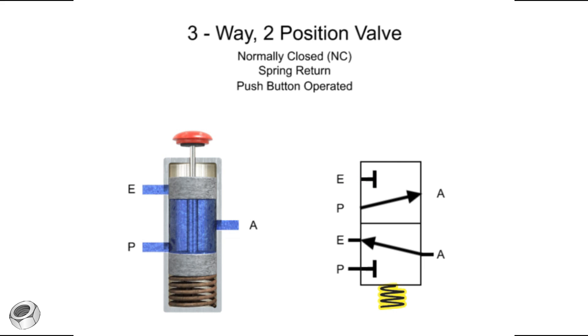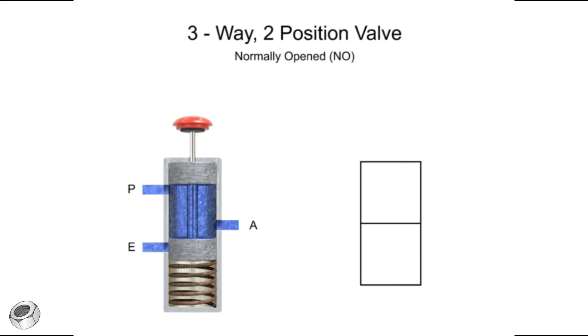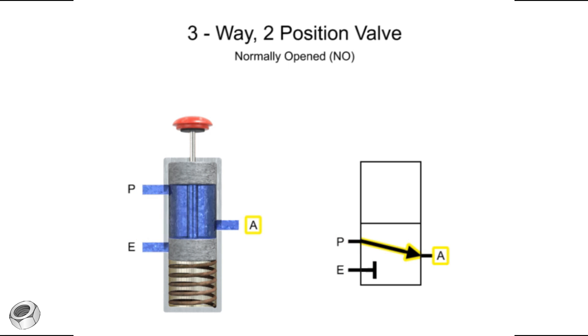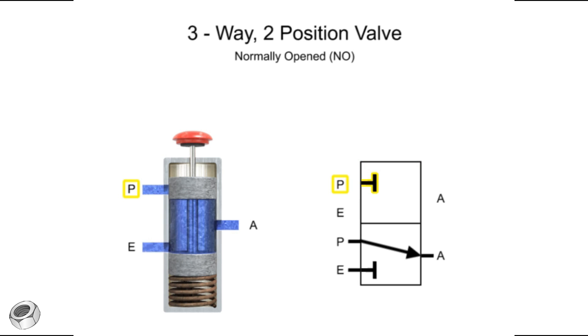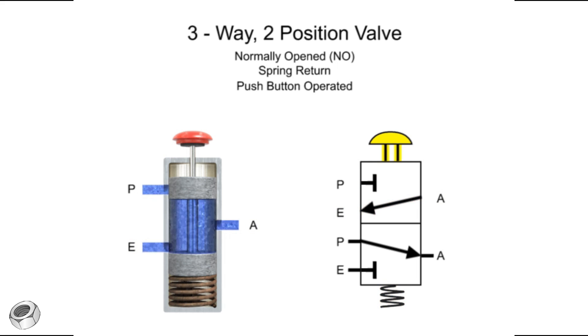The valve is also spring return and push button operated. Here is another three-way, two-position valve. It also has an inlet port P, exhaust port E, and output port A, but in a different configuration. In its normal position, exhaust port E is blocked and fluid flows from pressure port P to outlet port A. In the second position, pressure port P is blocked and fluid flows from outlet port A to exhaust port E. The valve is also spring return and push button operated.